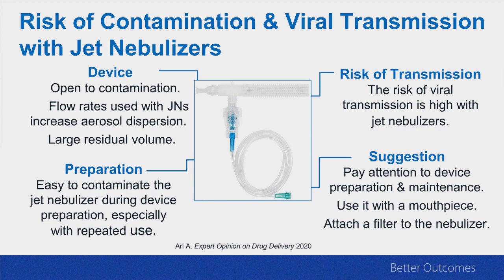If you use this device in a spontaneously breathing patient, your patient may take the mouthpiece and breathe through this device. But the secretion may drop into the nebulizer and contaminate the device. The other problem is that if you use this device in ventilator-dependent patients, the nebulizer will be below the ventilator circuit, and the condensate may drop into the nebulizer reservoir and once again contaminate the device. So those are the issues with the jet nebulizer, and it is easy to contaminate the jet nebulizer during device preparation, especially with repeated use.